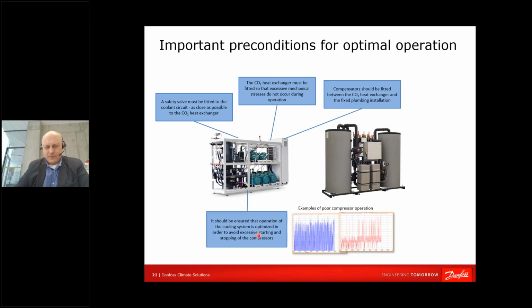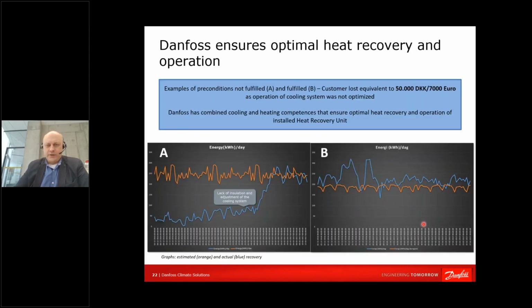And of course, operation of the cooling plant should be set correctly to avoid excessive starting and stopping, and we have an example of poor compressor operation. As regards insulation, we have a brown line which shows the desired result, and on the blue line we see the real gain. What we're speaking about here is poor insulation, and the customer lost some 7,000 euros on the application because the system was not optimized and not insulated.